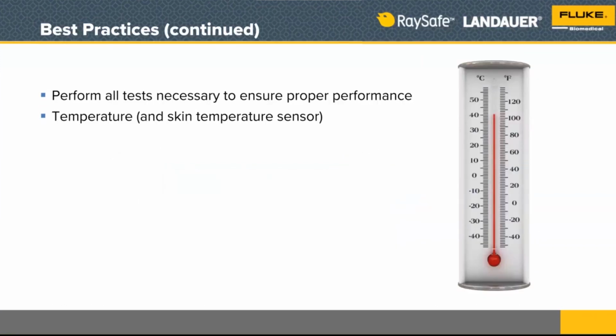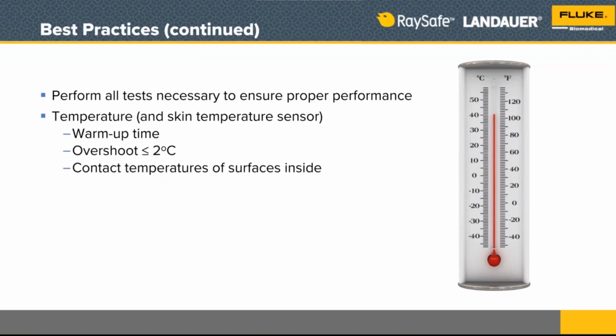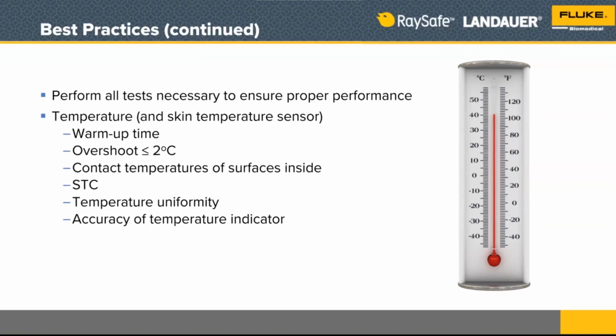Perform all the tests necessary to ensure proper performance. So that's temperature, certainly the warm-up time, the overshoot, contact temperatures of the surfaces inside to make sure the baby can't get burned on a hot surface, STC, temperature uniformity across the chamber, which you'll get by data logging all of those temperature measurement locations, and the accuracy of the temperature indicator itself. Temperature control and making sure it's working, and the skin temperature sensor, because that's one of the ways we're going to servo control the heater.